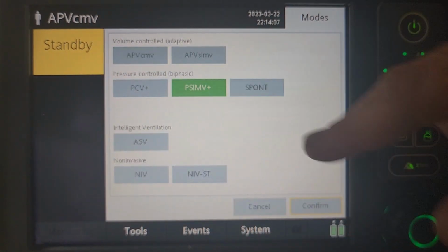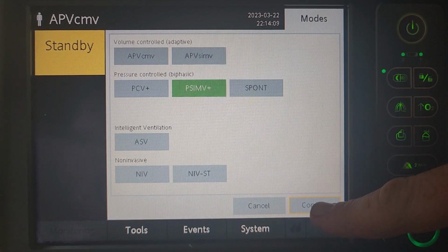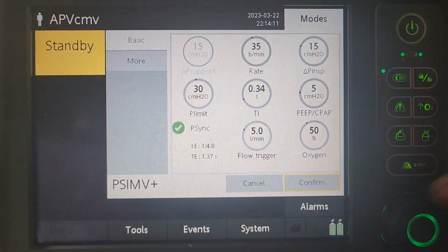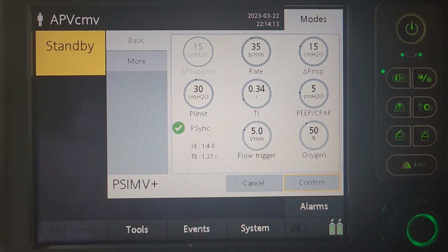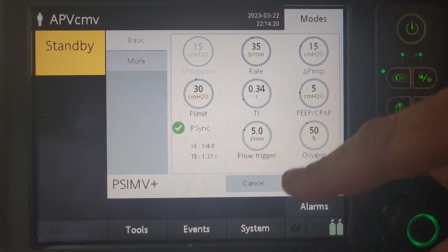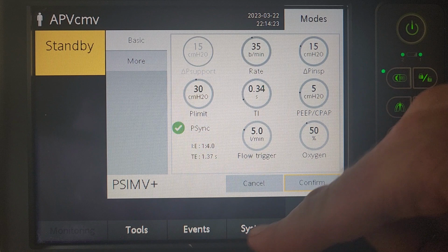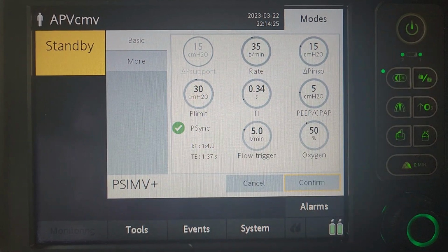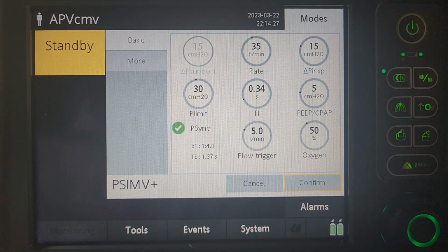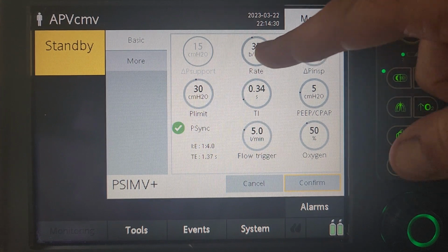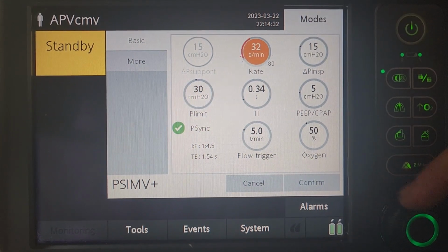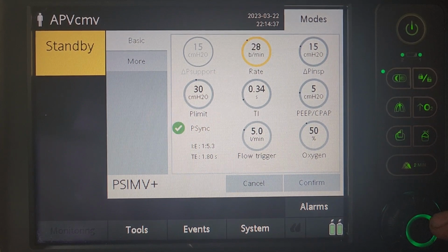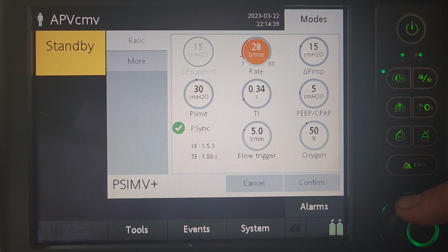And we're going to switch to the PSIMV for pressure support. So we're at pressure support, and you'll see this default settings screen here. So we want to make a couple changes right off the bat for the PSIMV plus. So you'll notice it defaults to an I to E ratio of 1:4 and a rate of 35. So for this age group, we want to go to the lower limit of what's normal and start. Now we'll start somewhere around 28 or even 30.